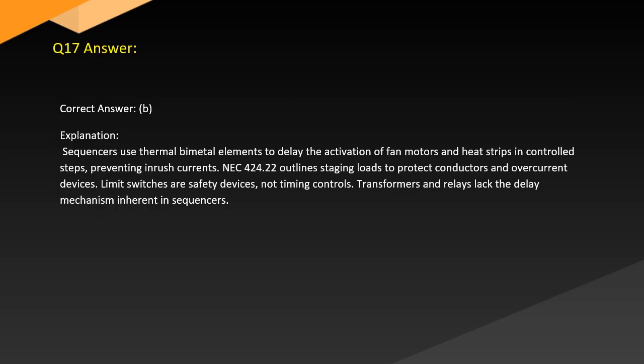Answer. Correct answer: B. Explanation. Sequencers use thermal bimetal elements to delay the activation of fan motors and heat strips in controlled steps, preventing inrush currents. NEC 424.22 outlines staging loads to protect conductors and overcurrent devices. Limit switches are safety devices, not timing controls. Transformers and relays lack the delay mechanism inherent in sequencers.